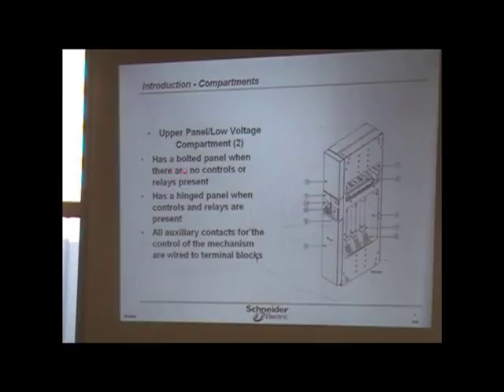It has a bolted panel where there are no controls or relays present, because this is not a motor control center. So there's nothing there. But it's identical, that's what I'm getting at. It's funny how people say, well, what's the difference? Well, once again, all this is a switch. It has no controls of any kind. The controls that would control this contactor would be up in here. When I say controls, that could be the permissives that are not connected to the contactor itself, because the contactor would have been at the bottom.